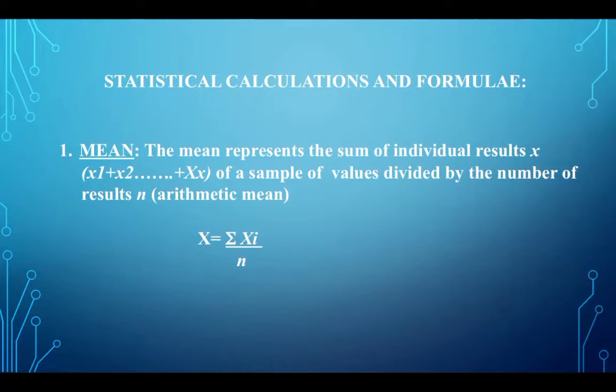You have some confusion in your mind. Suppose the previous CV is 2. How will you use that? How will you calculate the standard deviation from this 2? Using the formula, the mean. Okay, I got your point now. How will you set the lab mean, because for that you require a mean also? In the first month, which mean will be used by you? This is what I'm asking.